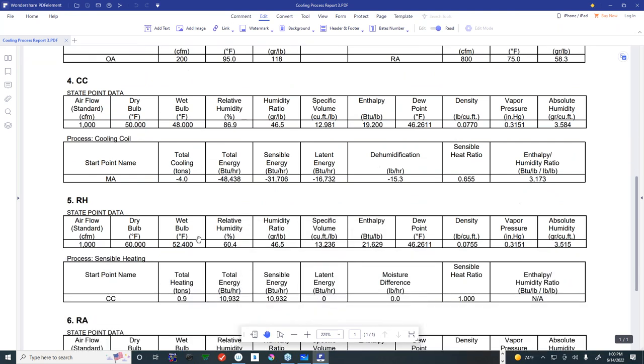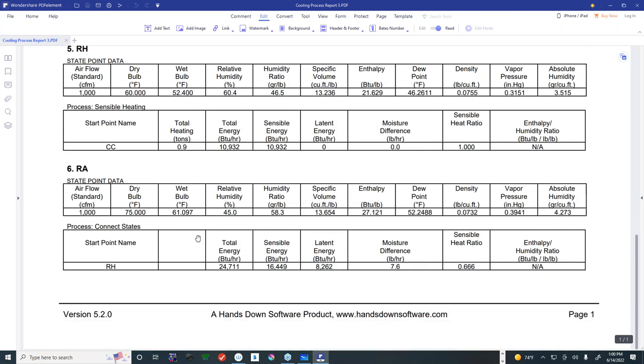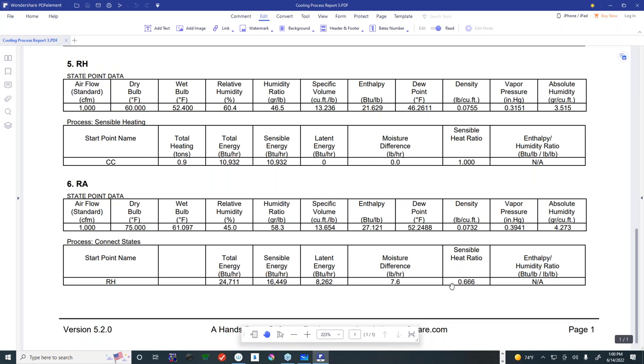And then this represents down here the room air conditioning. And if you'll notice, the sensible heat ratio over here is approximately 0.666 or approximately 0.67. So that 0.67 is the ratio of the sensible heat divided by the total heat in our little psychrometric analysis.